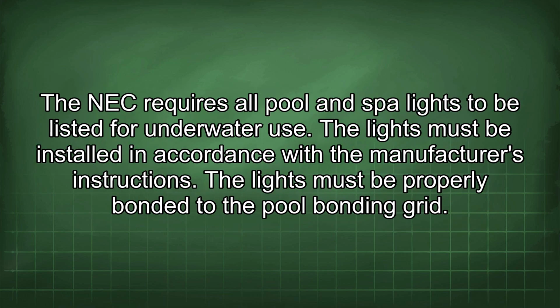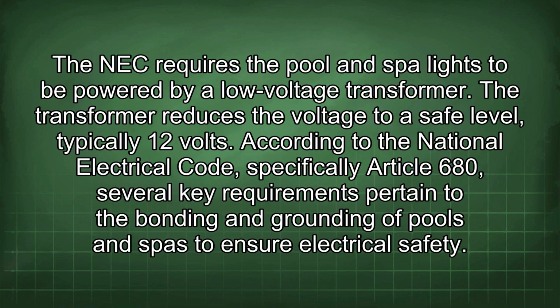The NEC requires all pool and spa lights to be listed for underwater use. The lights must be installed in accordance with the manufacturer's instructions. The lights must be properly bonded to the pool bonding grid. The NEC requires the pool and spa lights to be powered by a low voltage transformer. The transformer reduces the voltage to a safe level, typically 12 volts.